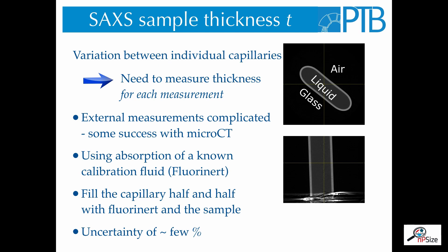But still, we need to measure the sample thickness for each individual measurement, because these capillaries are not all the same. There has been some success by using micro CT to measure the optical path of such a capillary. Of course, micro CT is a lot of effort and we cannot do this for every single measurement. Instead, we use the absorption of a known calibration fluid, fluorinert, which is known to not mix with water. Then, we fill the capillary half and half with fluorinert and the sample under test, and we can determine the optical path via the attenuation of the fluorinert. This allows us to measure the sample thickness with an uncertainty of a few percent.